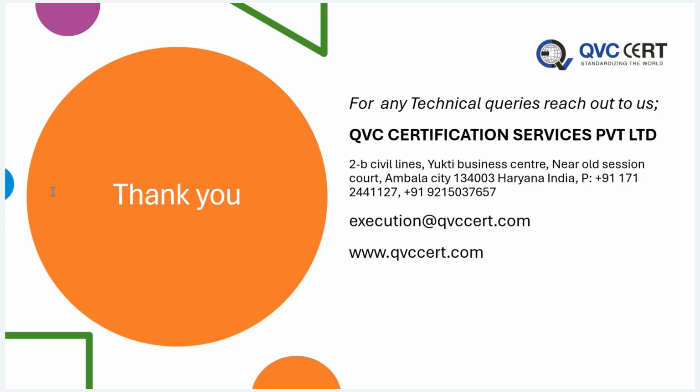If our device is class B and the predicate device is class C, and the intended use is also the same, can we consider the predicate device for approval? Your question is a little complicated, Ms. Vaishnavi. Let me remind you of the CDSCO rule. If you are claiming a predicate that is considered a class C device, then your device can't come under class B. It comes by default under class C, because CDSCO has directly written in its rules that the higher classification is preferred if the predicate you are claiming is higher risk. You cannot claim class B if you are claiming a predicate to be class C. So you can consider it a predicate device, but the classification will be upgraded. Hope this answer is suitable for you.